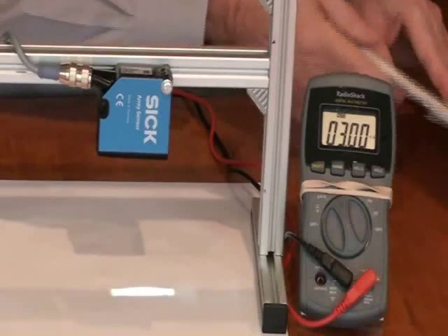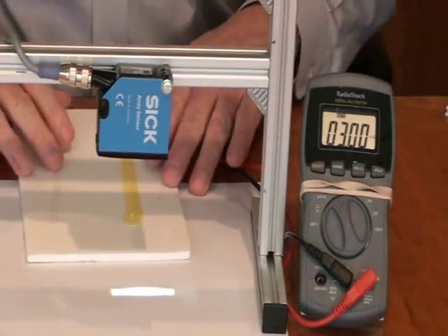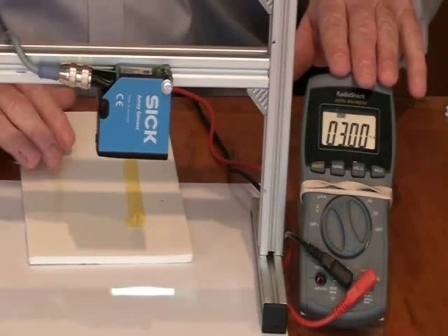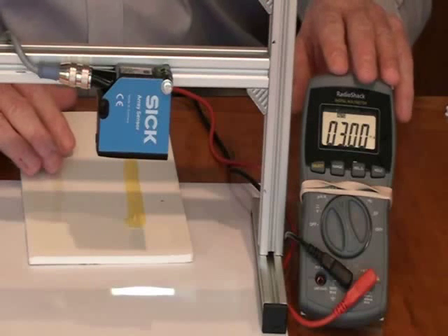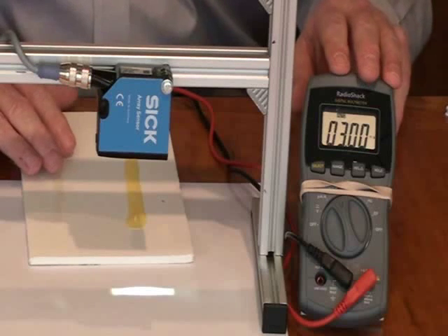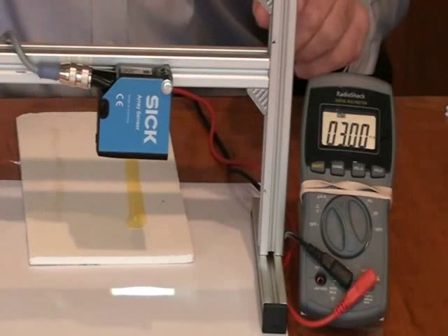What it's doing is it's measuring down there, and we're getting a no-read out of our analog signal. The sensor itself will produce a 4 to 20 milliamp analog value, which will have a direct correlation to the width of the target against the background.